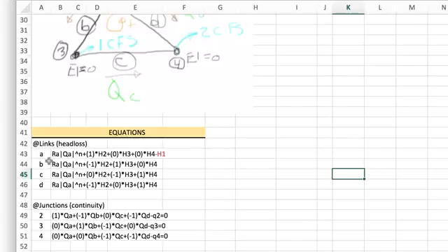So the R would symbolize the resistance factor for each pipe, calculated from the length, the diameter, and the roughness factor that we're using, whether that be Hazen-Williams, Chezy-Manning, or Darcy-Weisbach. So essentially the equation is RQ to the N, and we're going to do Hazen-Williams, so the N would be 1.852. And then in parentheses we've got a number 1, 0, or -1 showing whether the head at the nodes are to be included in the head loss balance for the pipe.